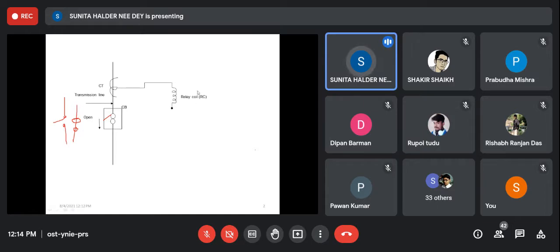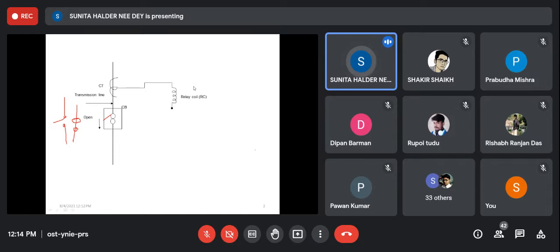So that's why there is a relay coil. The CT will measure the current every time and energize the relay coil. The relay coil will be energized to an extent that it can close a circuit when it crosses a threshold limit. That means the relay coil will not be energized to a sufficient voltage when the current is 500 ampere, but it will be energized to a sufficient voltage when the current is 2500 ampere. But it does not mean the relay coil will energize only at 2500 ampere. It will start to get strength after 500 ampere.